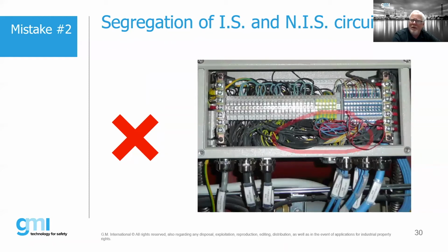The reasoning behind the separation and segregation between IS and non-IS circuits is to make sure that we have no inductive currents that could pass from a power conductor into an IS circuit through air, right? So we have to make sure that we segregate our IS and non-IS, because we do not want that to take place. And there are different ways. In addition, Bob, if any of this wiring which has current that is uncontrolled because it's non-IS, they could melt down and melt the cables, you know, the IS cable, and make a short circuit or whatever.